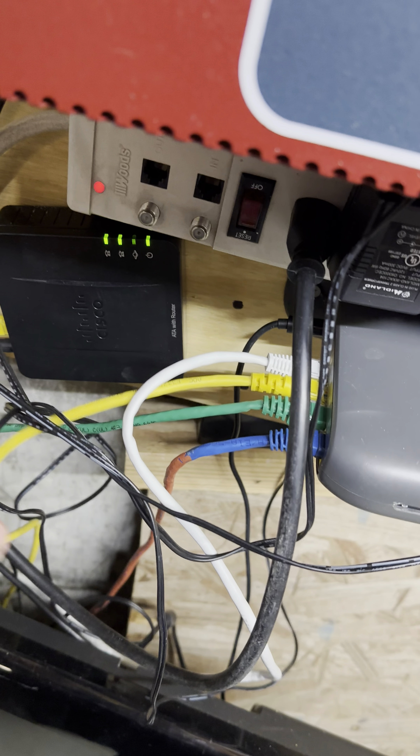This is the MS9200 UDLS. I've got some other stuff in here — some tools and door holders. It's a 24-volt system with two transformers that do 12 volts each. It's wired directly into the wall outlet, though there is a switch — if I flip it quickly enough it'll go into AC power fault, as you can see it now says 'AC fault.' I don't want to fully power it off though because I don't have batteries yet.